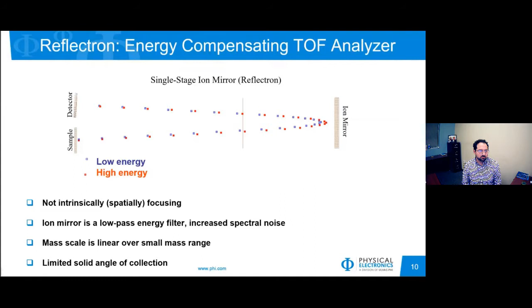Another type of energy compensating analyzer is a triple ion focusing time of flight mass analyzer, also known as the TRIFT, and this is what Physical Electronics sells. It works slightly differently than the Reflectron in that instead of using a mirror, it uses 3 ESAs to refocus the kinetic energy of the ions, and they work together to focus the energy.